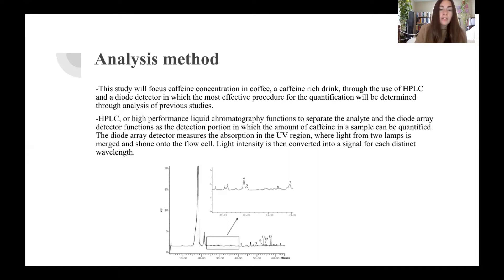So HPLC, or high performance liquid chromatography, functions to separate the analyte, and the diode detector functions as the detection portion in which the amount of caffeine in the sample can be quantified. The diode detector measures the absorption in the UV region, where light from two lamps is merged and shone onto a cell. Light intensity is then converted into a signal for each distinct wavelength.